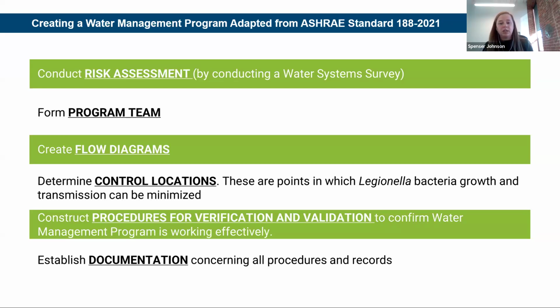Are we going to do Legionella sampling to confirm that all of our actions are working? Maybe you're taking disinfectant residuals at fixtures throughout the facility, taking a sample at the point of entry, seeing what level you're getting from the municipality, and then taking samples throughout to confirm whether there's been enough flushing going on and the water is being moved through the facility. Or maybe taking some samples for HPC levels, heterotrophic plate counts, getting an overall bacterial level, trying to confirm if you're within the limits that the EPA has set.